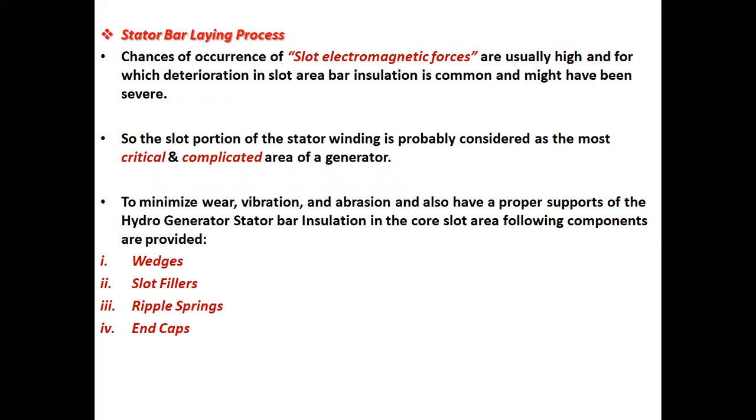Stator bar laying process. Chances of occurrence of slot electromagnetic forces are usually high, and for that reason deterioration in slot area bar insulation is common and might be severe. So, the slot portion of the stator winding is probably considered the most critical and complicated area of the generator.